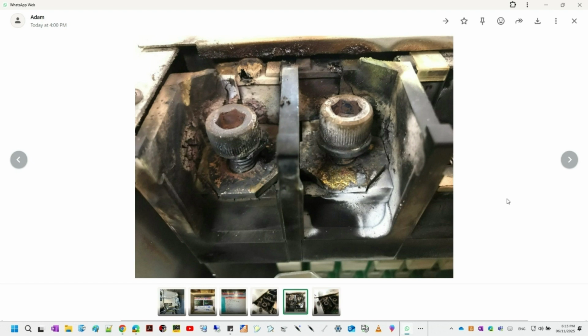This thermal runaway process just accelerates. It generates escalating amounts of heat until that connection point literally melts, starts arcing, maybe catches fire, and causes catastrophic failure of the cables and whatever component it was connected to, in this case, the expensive spindle drive. Wow. It's actually incredible that something as seemingly simple as a slightly loose bolt, through this thermal runaway process, can cause such dramatic, expensive destruction. So, okay, what are the big actionable lessons learned here for preventing this specific thing from happening again?